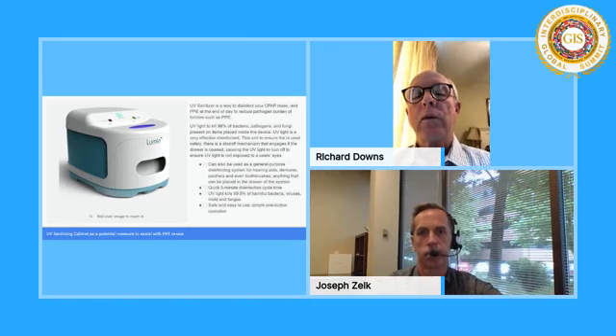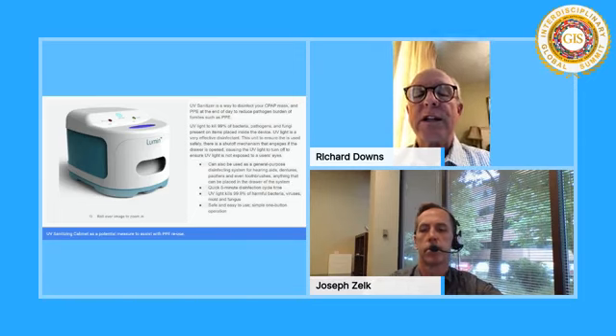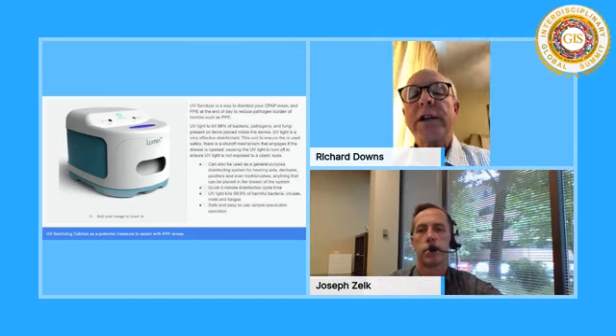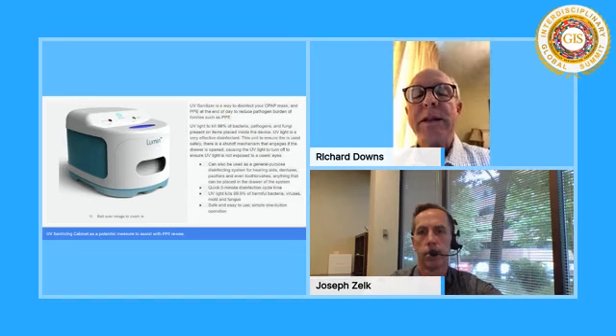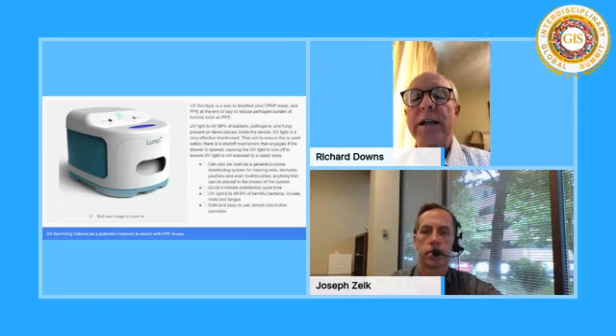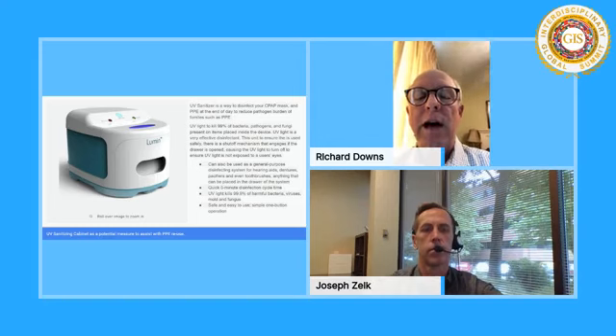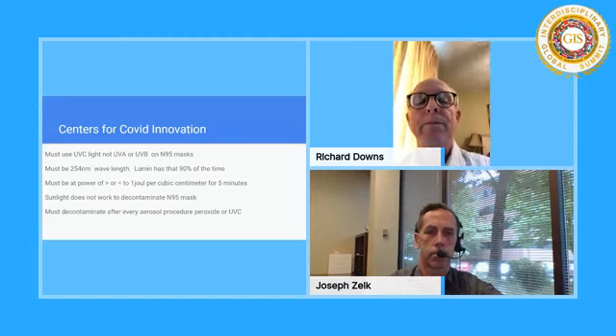Here's the one that we found that I believe is very effective. This one's been shown to use UVC light. UVC light is what you want for re-sterilizing or repurposing a mask. You can do it in 5 minutes with this machine at 254 nanometers of wavelength. And you want to make sure it's UVC light, not UVA or UVB light. You can't use a nail salon ultraviolet light for repurposing your masks in the office. It's not going to work, but these do work.